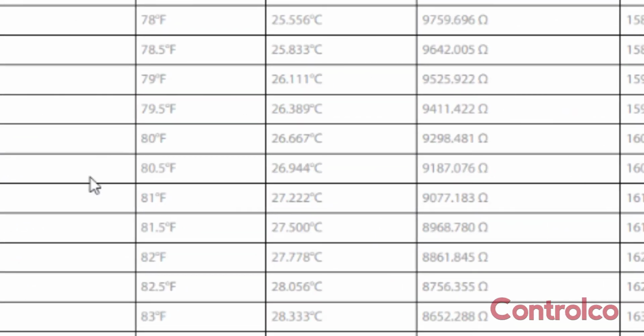So I can see at 9,500 ohms, I was 79 degrees, and 91, I'm at 80.5. So somewhere in there, right around in that range, is what my room temperature is. So yeah, my house is a little warm right now. And that's it. And that's all you have to do to check one of these sensors out.